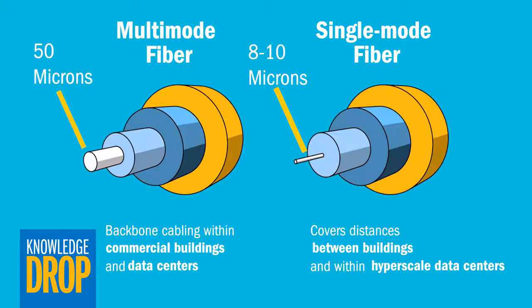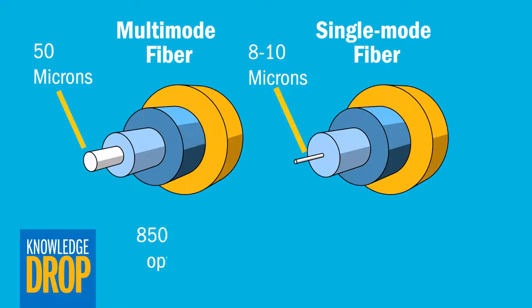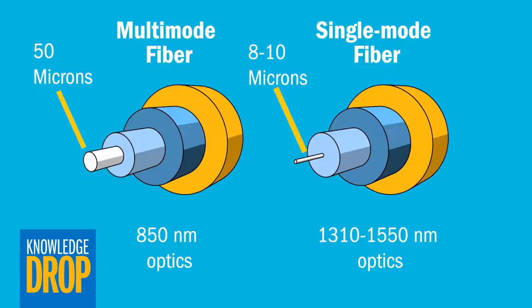Multimode fiber is a more economical choice for most commercial buildings and smaller data centers. Multimode infrastructure has the advantage of utilizing lower-cost short wavelength optics operating at 850 nanometers, which drives lower overall system costs compared to the more expensive single-mode optics, which use longer wavelength optics in the 1310 to 1550 nanometer range.